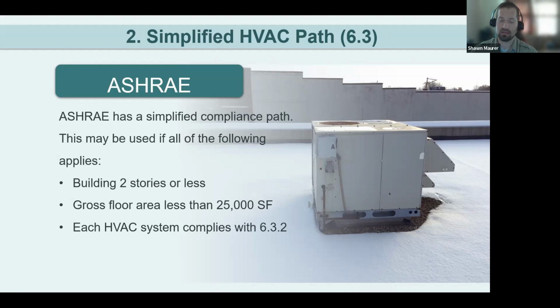As Ryan touched on earlier, when looking at an overview of the compliance paths, ASHRAE does have a simplified path that the IECC does not. And these will not be added to the IECC in the 2021 version. So these are exclusive to ASHRAE's compliance pathway. It's unique to ASHRAE in that it's taking into consideration if you've got a smaller system and you don't really need to consider all these advanced controls for it. Even with the IECC, those advanced controls get phased out through the regulations and requirements depending on the size of the system. ASHRAE just takes that and separates it out into its own section so it's easier to follow. You don't have to muddle through all the compliance requirements in the full compliance section.